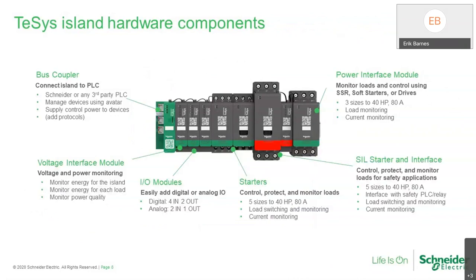So it all starts with a bus coupler. This is kind of the brains of the operation, if you will. It is going to house all of the configuration for everything connected to it, downstream to the right of it. It's going to be the communication gateway, so it's going to communicate to all the devices downstream. It's going to communicate upstream to your PLC, and it can work with a Schneider PLC. It can work with a third-party PLC. Anything will work there. It's fine.